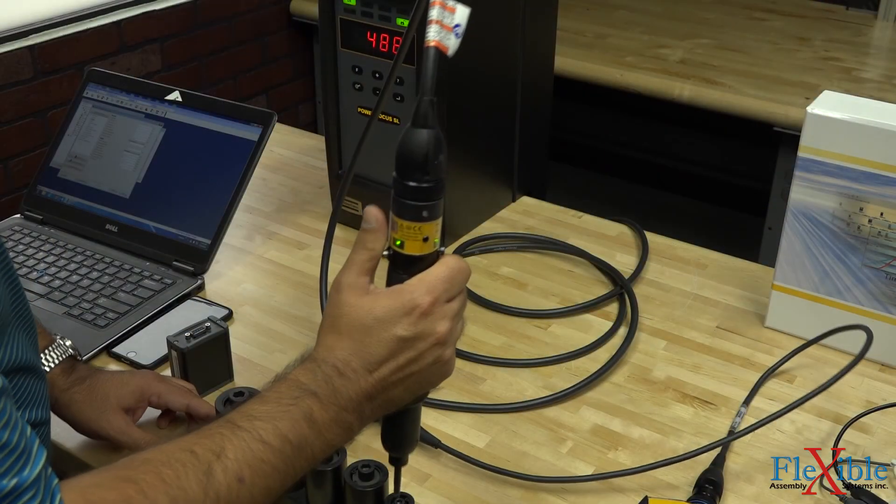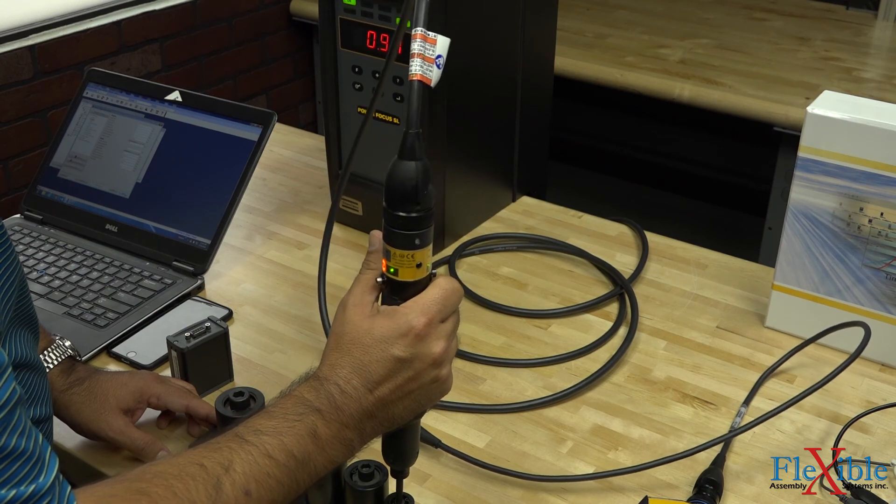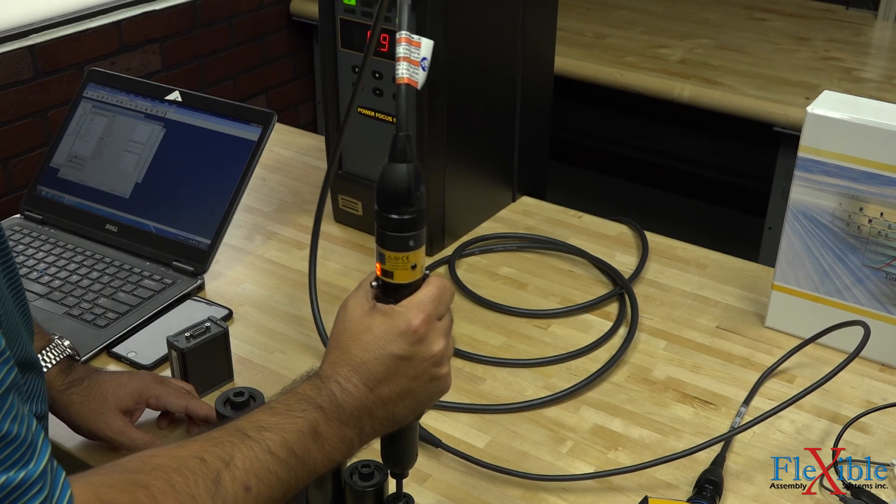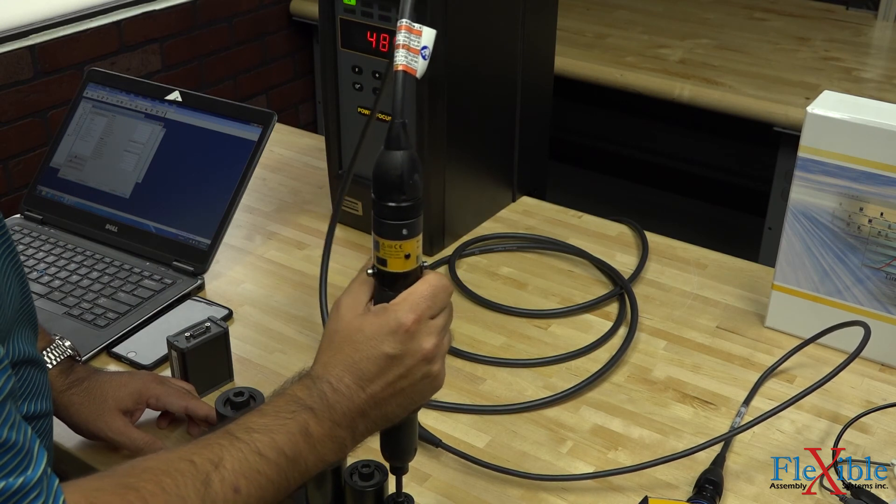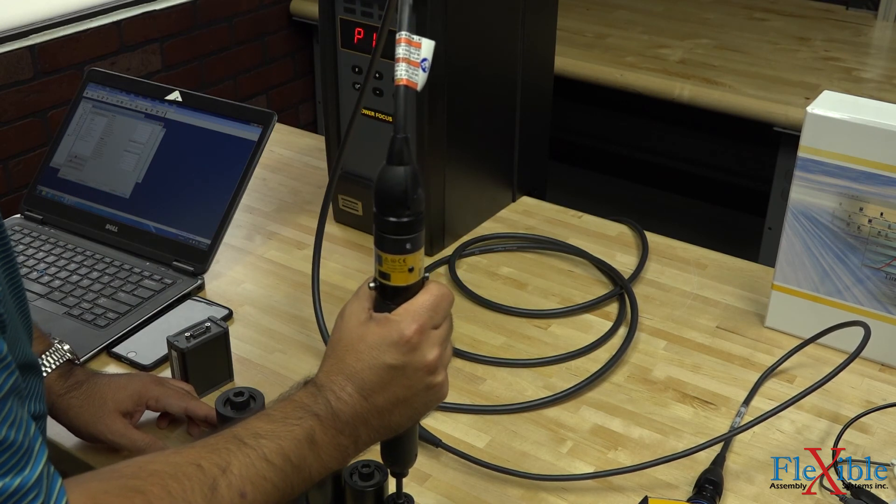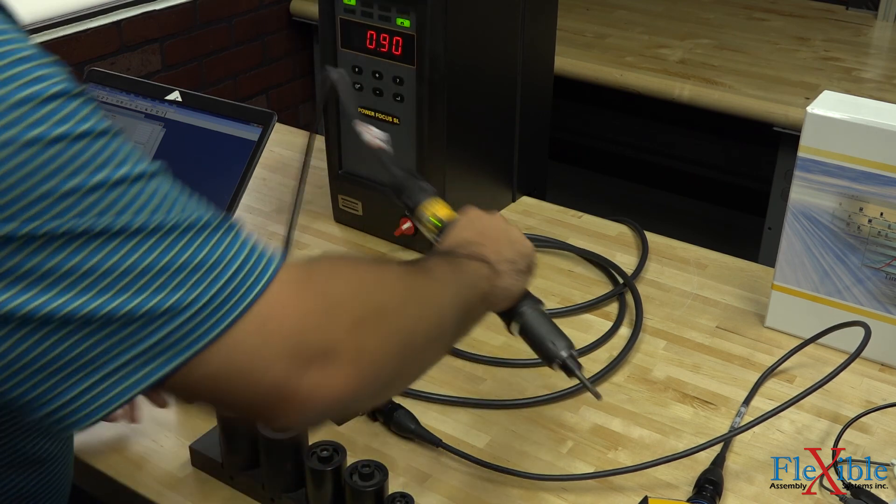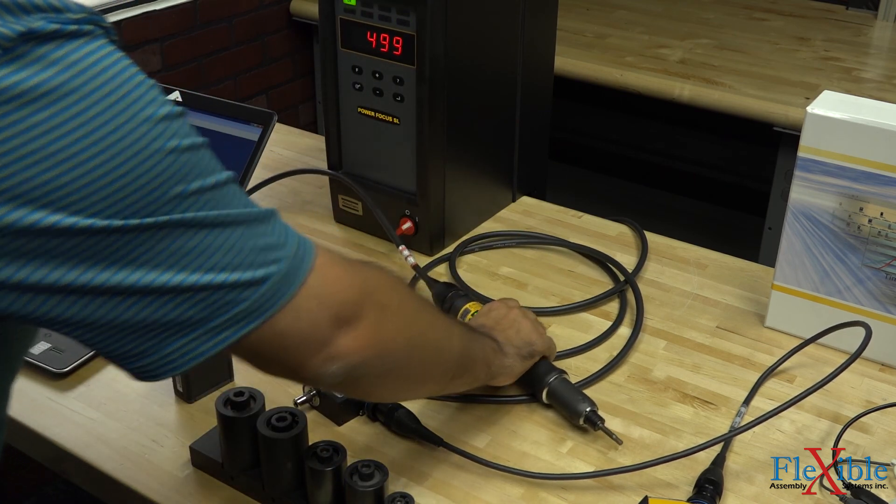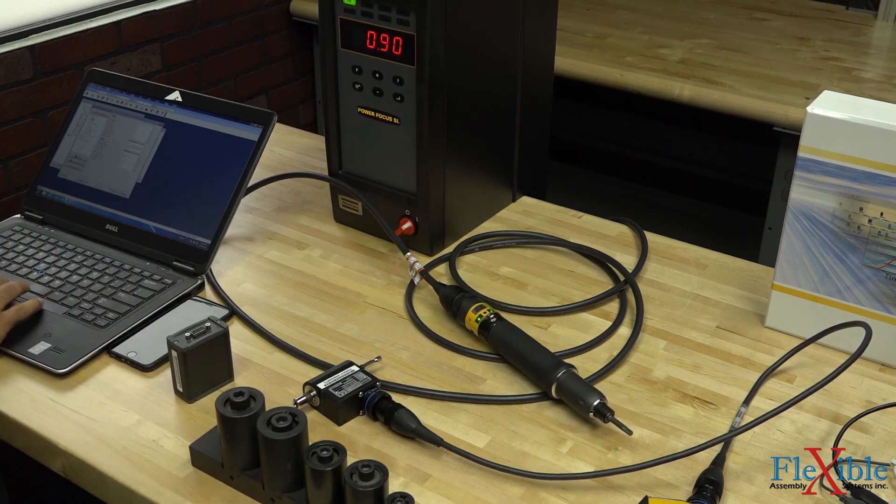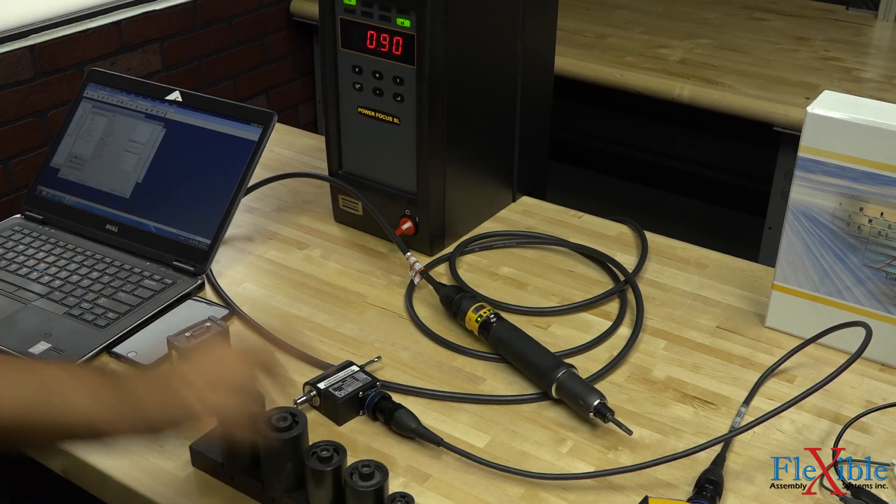Now that our pset is ready, we will do a run down on the soft joint with no transducer attached. As you see, we hit our mark of 0.9Nm perfectly according to the controller.